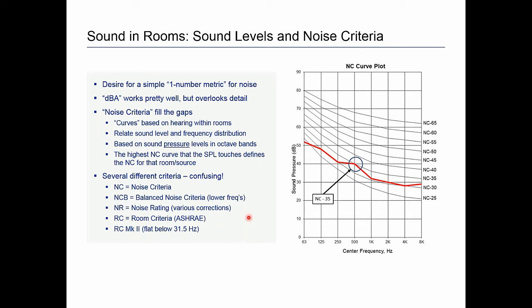One important thing to note is that you cannot plan as an equipment manufacturer for a specific noise control rating. The only thing you have control over is the sound power and the shape of the spectrum from your equipment, because in the end the noise criteria depends on the room itself — its size and the amount of acoustical absorption in the room.